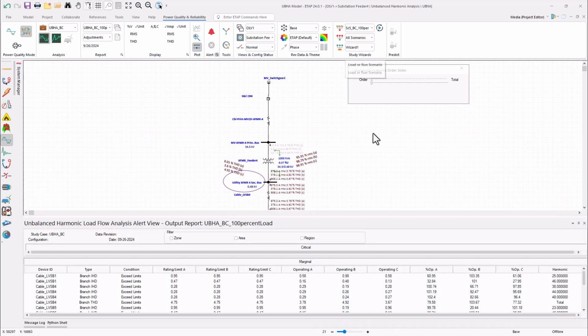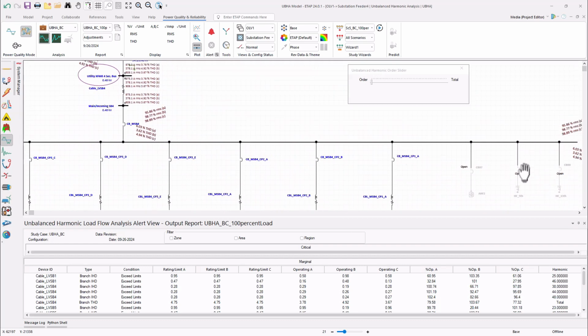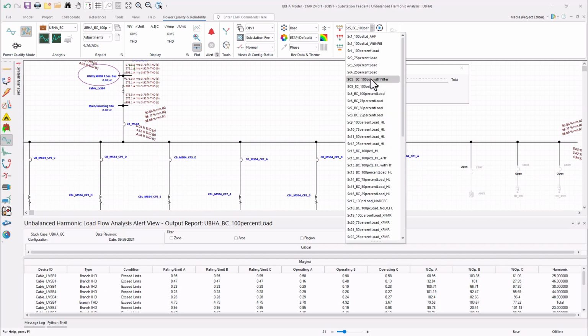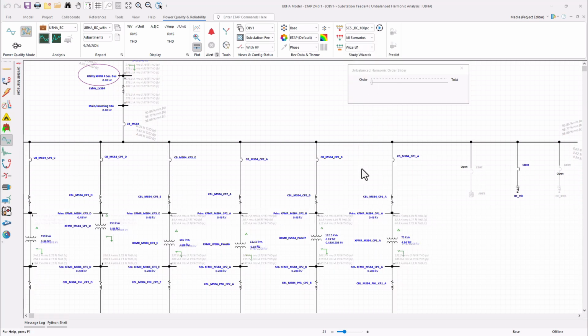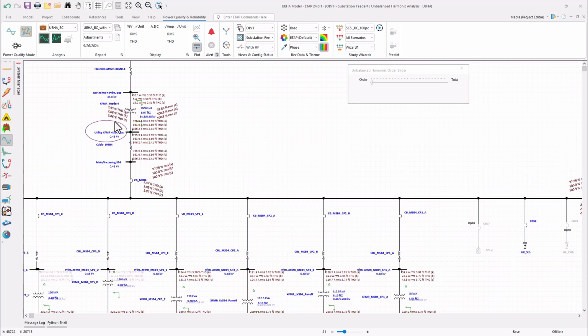Now let's also run the case where we have a passive filter sized for the 5th harmonic order. So this is one of the solutions provided to the client for addressing the harmonic distortion issues noticed in the field due to the harmonic content from the EV chargers. So now we have the results for this scenario. Voltage distortions at this bus have reduced, and the current distortion on phase B for this cable also has come down from 4.92 to 3.56%. Let's take a look at the plot.